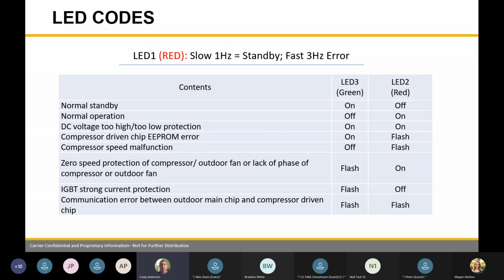So your outdoor unit is going to have codes, plus your indoor unit is going to give us codes as well. So be mindful, if you're looking at a code on the inside that's not making sense, it could be the outdoor unit that's faulting and giving you a code. So make sure before you go to the job site that you're mindful of what unit you're going to work on and what kind of codes we're going to be looking for when we get there.